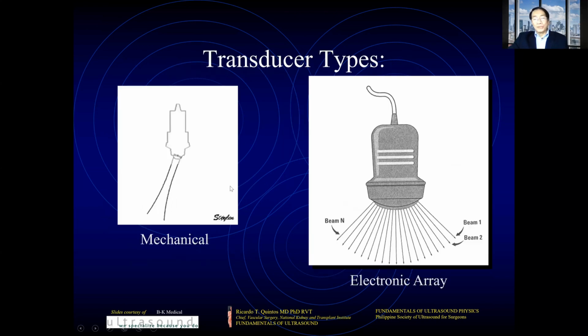So this is the mechanical transducer. You will see here that it emits a wave, and the mechanical movement of the array allows it to sweep back and forth so that there will be a collection of ultrasound reflections, which is then collected by the central processing unit, analyzed and brought out to the display monitor. But the electronic array transducer actually has multiple beams being transmitted out. So it's not a mechanical event now transmitting beams at different angles, but we now have multiple beams coming out from the array. There is an array of crystals that will allow the beam to be propagated away from the transducer.